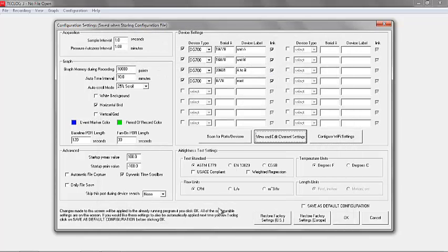Okay, those are all set. And then our test standard we're going to use is the Canadian General Standards Board. That's the test that's been in TechTite all these years. It's a multi-point test that goes from 50 pascals down to 15 in increments of 5, so 8 points. With the pre and post baseline, we're going to speed that up a little bit and just do one baseline and just do 50, 40, 30.